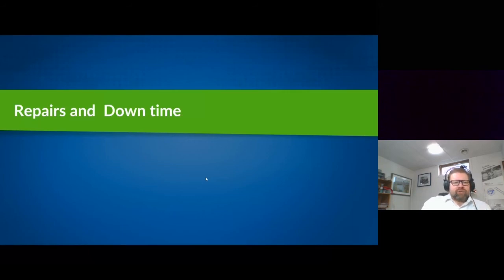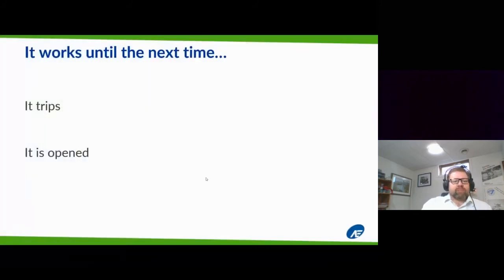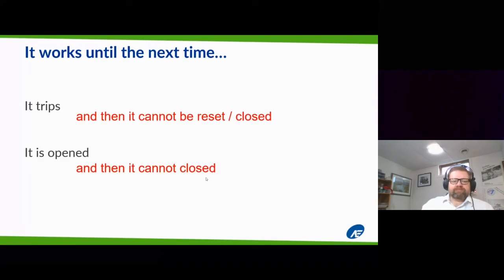Now let's take a look at what's going to happen when these breakers don't do what they're supposed to do. If it works until the next time it trips, you might find that it cannot be closed or reset. Now that's fine, sure, no one got hurt, but unfortunately you can't turn the lights back on. This typically happens with more expensive breakers, so your main breakers. So if something does happen, you trip the main breaker, you go to return it, and it doesn't go back into its normal state, and it just stays off. If you manually open it because of maintenance, you just can't close it again, no matter how much you try and lock it back into place. Now, these types of repairs, you typically can get somebody to come to site and repair it within 24 hours. It's usually mechanical repair.